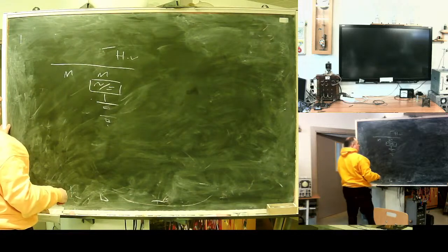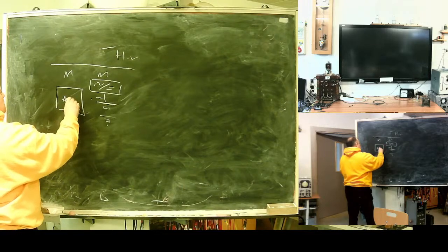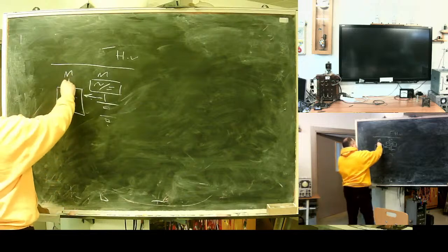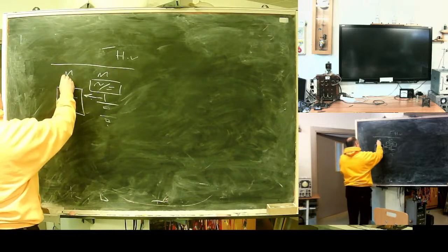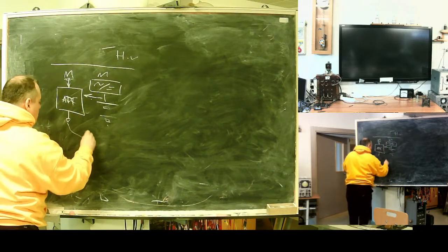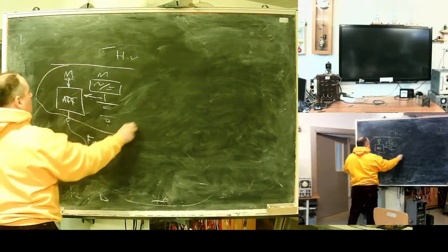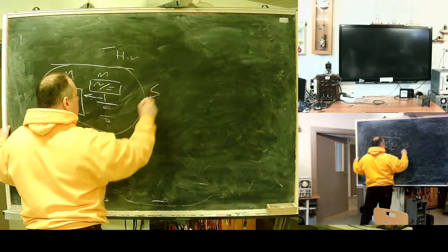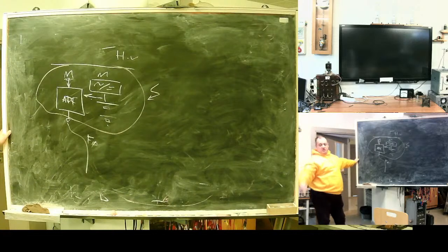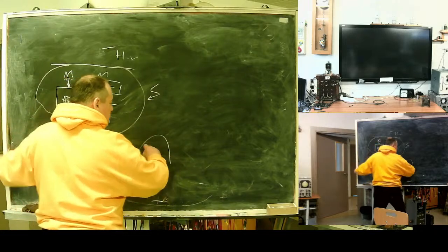Battery, this to power the ADC, analog to digital converter. There should be a load resistance, and then fiber optics. All this part is connected to the line, it's under high voltage. Fiber optics ensures insulation from the ground.